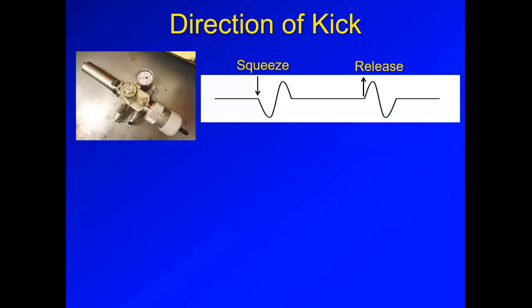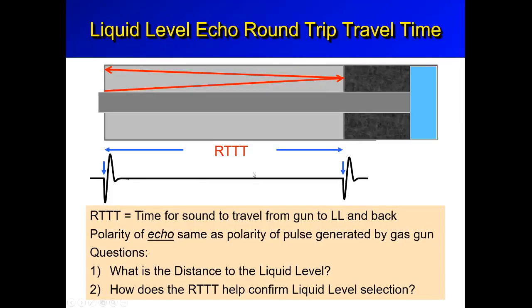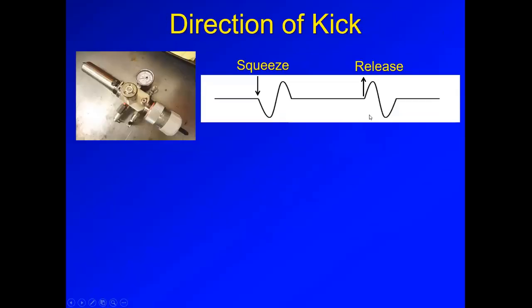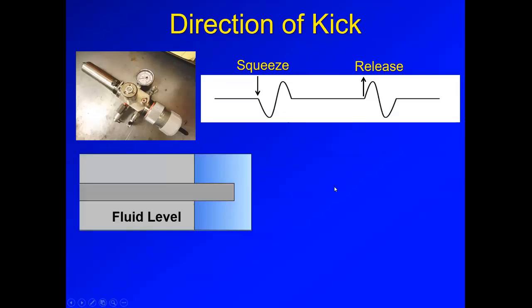We have to interpret the acoustic pulse, because in this case we see a down kick, but it could also be an up kick. We'll see some examples where you see down kicks and up kicks, and try to understand what that represents. Anytime you see a down kick - and this is just a test cap, if you have a microphone problem or want to check how the microphone is responding, you can put a test cap, close the bleed valve, check the background noise, squeeze the bulb, and you should see a down kick.